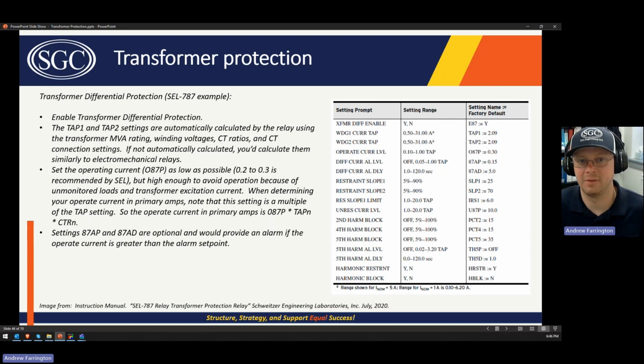There could be any number of explanations, but you want to know that because if it's a setting that you've come up with, you don't want to be the person that caused the transformer differential relay to trip for an out of section fault, taking out customers. They go there, the transformer lockout relay is rolled, and now they're going, oh, geez, is there a problem in the transformer? It's just not a good situation to be in. So just a word of caution.